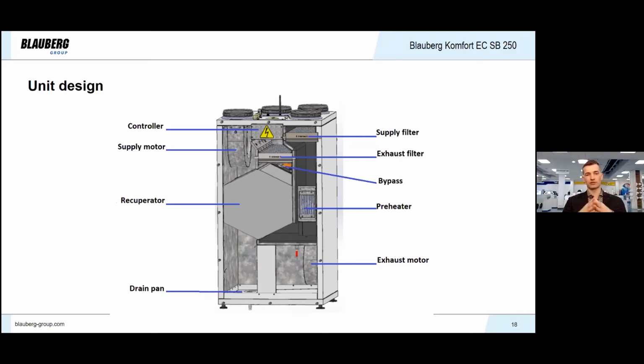We have already mentioned heat exchangers. There are two types, plastic one and enthalpic one. We have already mentioned fans with forward curved blades, impeller and EC motor inside. They give extremely low noise, so these characteristics would be very competitive for this unit. And it's worth mentioning that this unit has a bypass with Belimo actuator inside and an optional preheater of course.